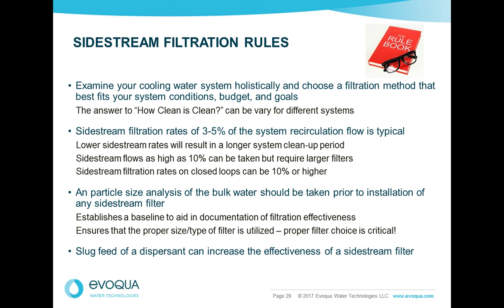Lastly, the filter is only going to remove what it sees. As Bob said earlier, the particulates tend to collect in the low flow areas, and they're going to stay there. Feeding a dispersant once in a while is going to help dislodge those particulates and get them into the bulk stream so the filter can remove them.